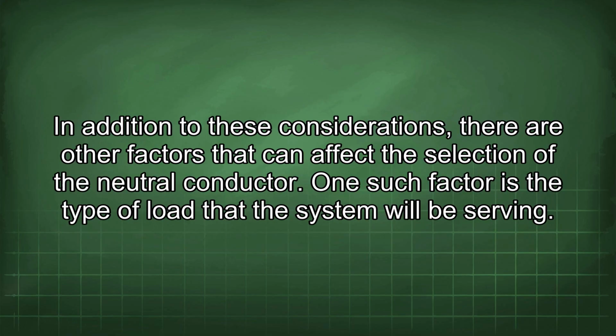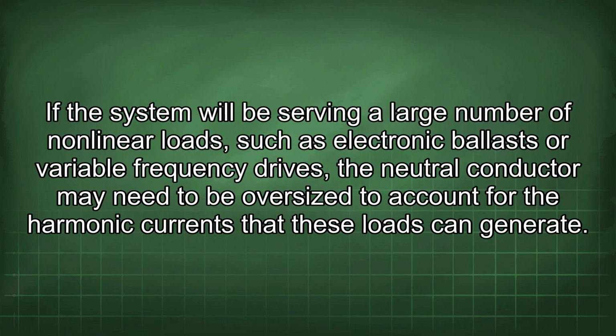In addition to these considerations, there are other factors that can affect the selection of the neutral conductor. One such factor is the type of load that the system will be serving. If the system will be serving a large number of nonlinear loads such as electronic ballasts or variable frequency drives, the neutral conductor may need to be oversized to account for the harmonic currents that these loads can generate.